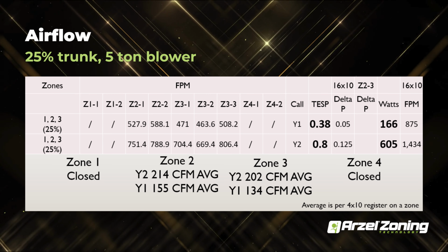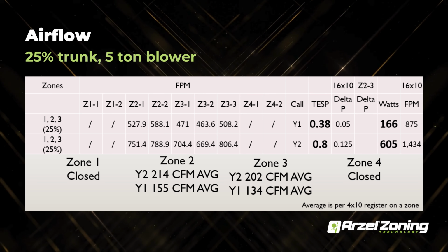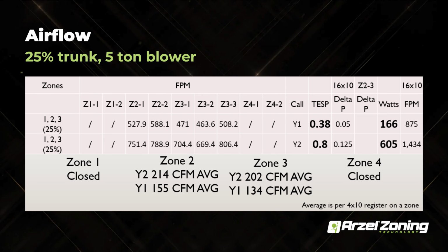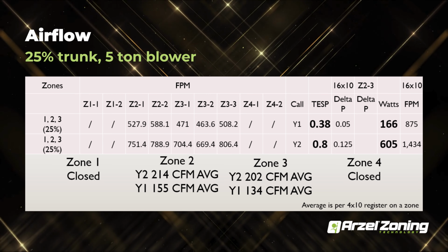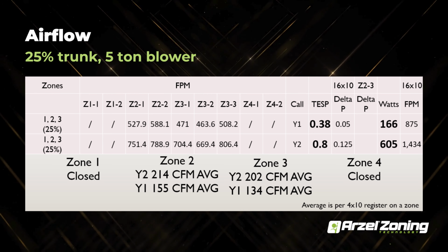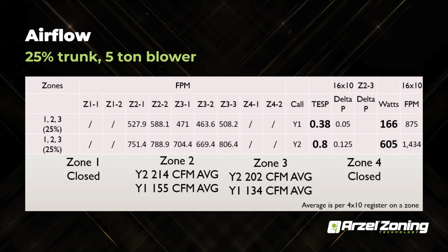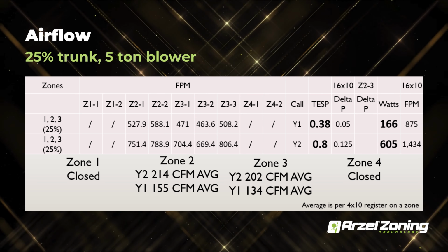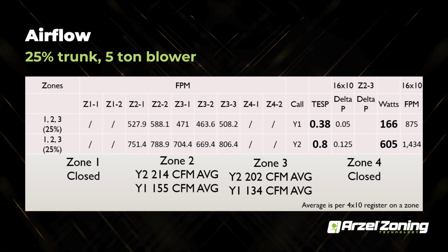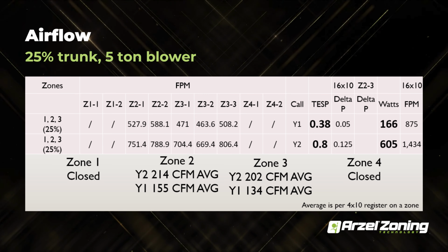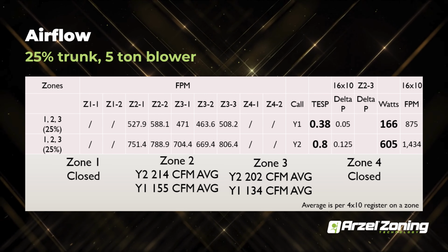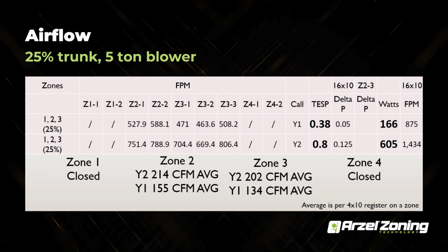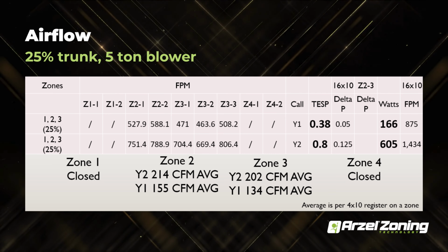You never want to exceed their maximum static on the equipment. So they're always going to have a 0.5 as their desired, and then they're going to have a maximum. You just want to make sure you're under the maximum. So typically about a 0.7, 0.75 is really where you're looking for that total system static pressure. And then with your wattage, you can see 605 watts. So you're using much more power and only 1,434 feet per minute out of the register. It's really not that much of a difference.